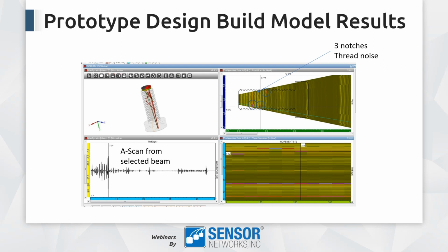This just shows you some of the things that we can do in that tool, where we can model the array, we can model the part, and even the defects. And so you see output here from the program where we can look at different simulated responses and even A-scans.